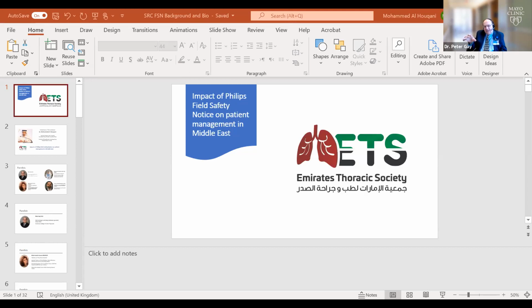If that's the case, then at this time, until further evidence is clear, we are clearly telling our patients not to use ozone cleaning. And fundamentally, we've been sort of querying this all along. Listen, ozone doesn't clean, it sterilizes. If you have something that's really dirty, you don't take the bottom of your bird cage and put it in ozone and clean it. It's still what's in the bottom of the bird cage. It's just got no bacteria in it. And you don't want to leave it there. So there's cleaning and there's sterilization. You still got to clean your device. So that would be my advice.